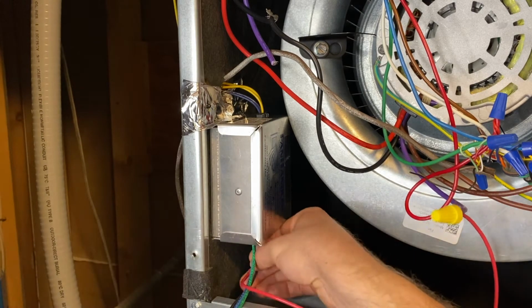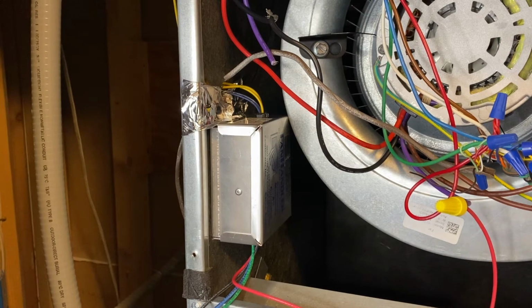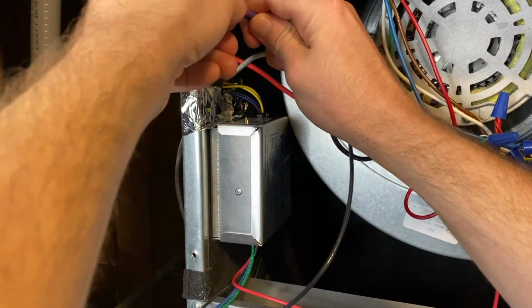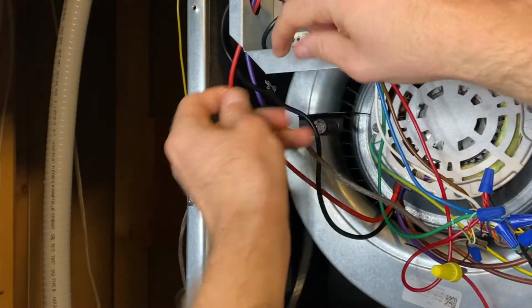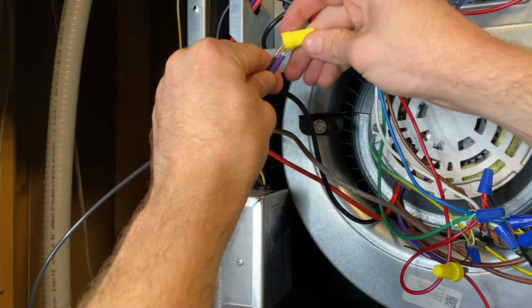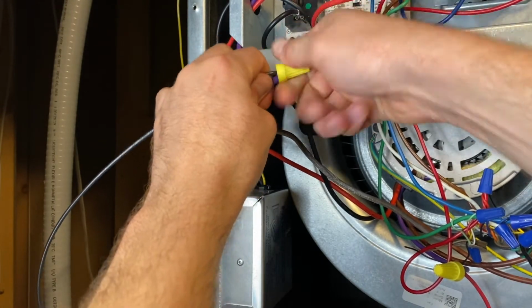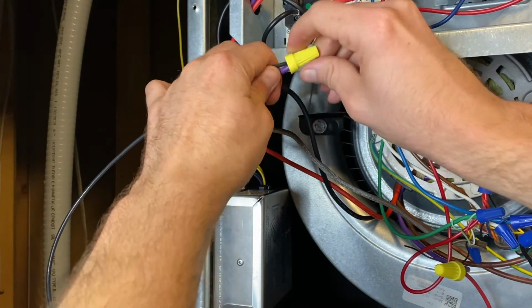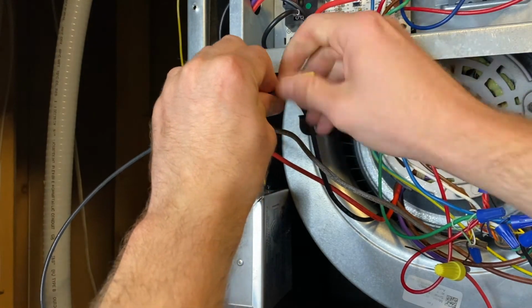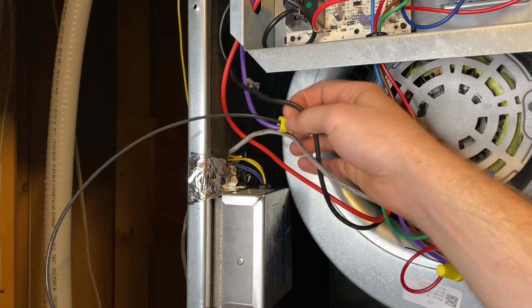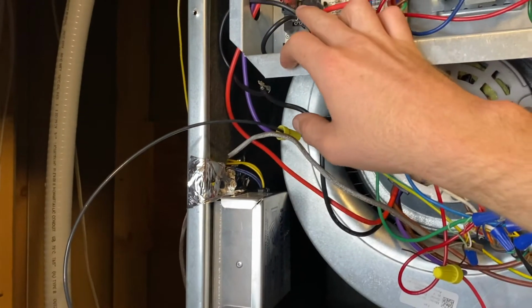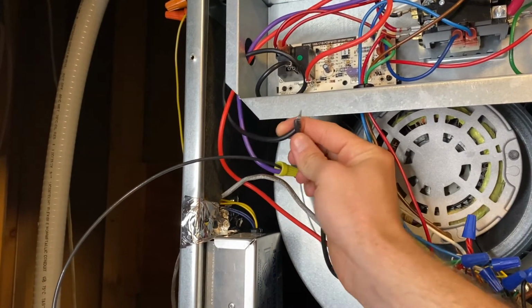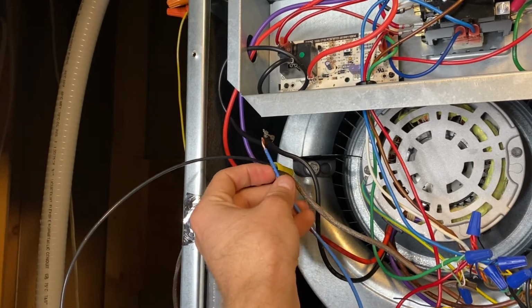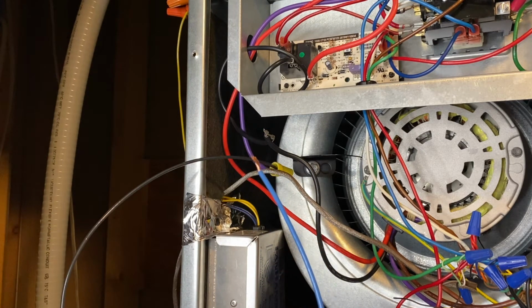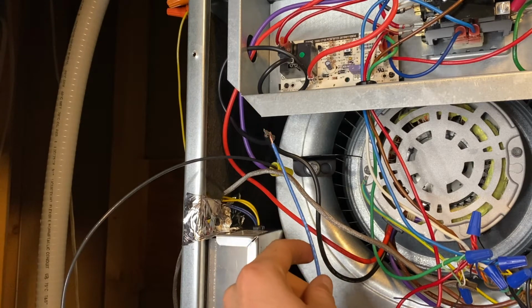And then the black wire, which comes out of the same hole on the fan handler, that'll go to the other side, the control board side of the purple wire. This black wire, which I've cut, goes from the speed selector we have up here to the motor. And we cut it, but we only cut it so we can tap this blue wire into this line. This blue wire is used for shunting radio frequency interference. So it just has to tap in to the wire coming from the speed selector board.